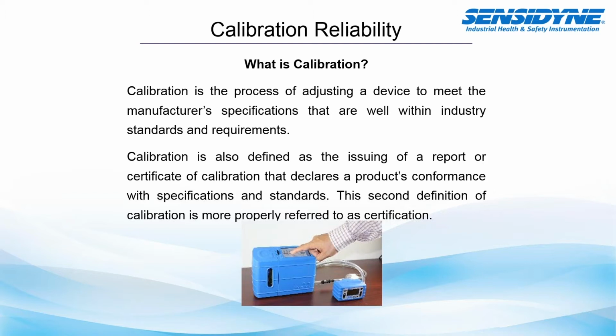So when we talk about calibration, there are different types of calibration that are out there, but calibration itself is the process of adjusting a device to meet the manufacturer's specifications that are within the industry standards and requirements. Calibration can also be defined as the issuing of a report or certificate of calibration that declares a product's conformance with a specification or standard. The second definition I mentioned is more properly referred to as certification as opposed to calibration. And as we proceed with this presentation, we'll talk a little bit more about those differences.